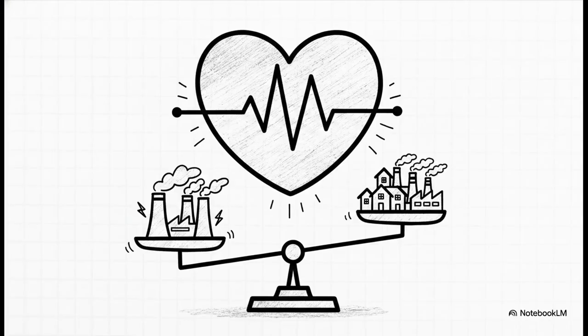The third and final pillar is frequency. The entire North American grid has to maintain a steady 60 Hz heartbeat across the interconnected system at all times. Frequency is essentially a measure of the real-time balance between power generation and power demand. If a massive power plant suddenly fails, generation drops below demand, and that heartbeat starts to slow down. If the frequency drops too low, automatic protective relays will immediately start shutting everything down just to prevent permanent physical damage to all that heavy machinery.